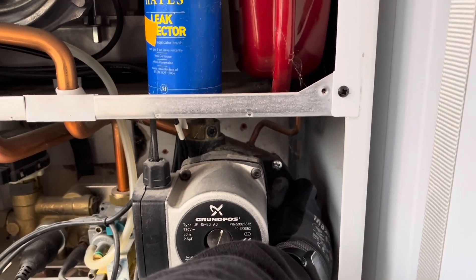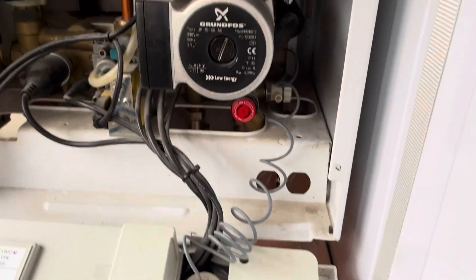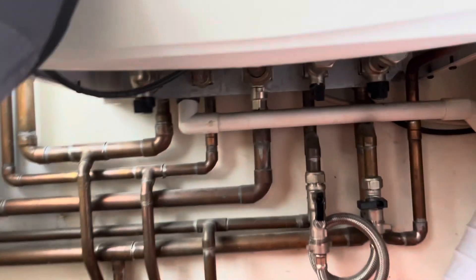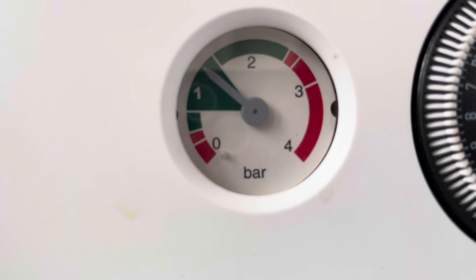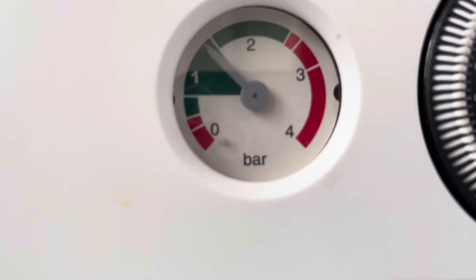Shut your drain off. Remove your hose, taking care not to spill any water on any of the electronics. Locate the filling loop and open both valves up to recharge the water pressure in the boiler between 1 and 1.5 bar. Note that the water hasn't drained the system because you've only had the one drain point open.